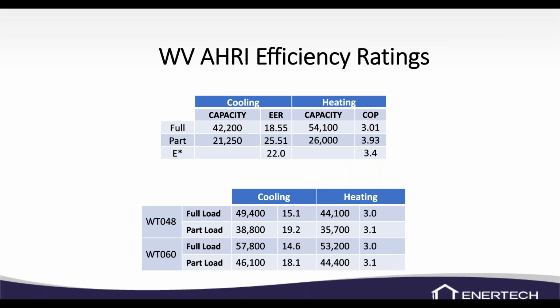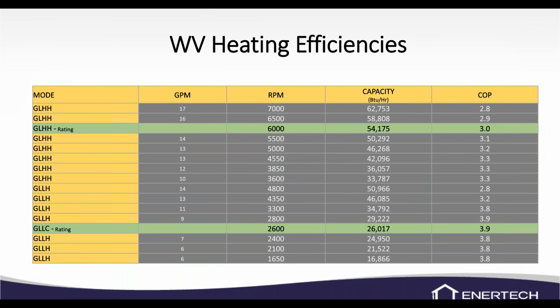But you can definitely see our EER and COPs when we're in part loads, which we're going to be running on the WV at some kind of part load quite a bit. So that's when we really gain our EER and our COP, or our efficiencies. We do have a little bit more of an expanded chart that'll show you the different RPMs and what the capacity and COP is. So you can see at 2600 RPM, we're running about a 3.9 with a capacity of roughly 26,000 BTUs.